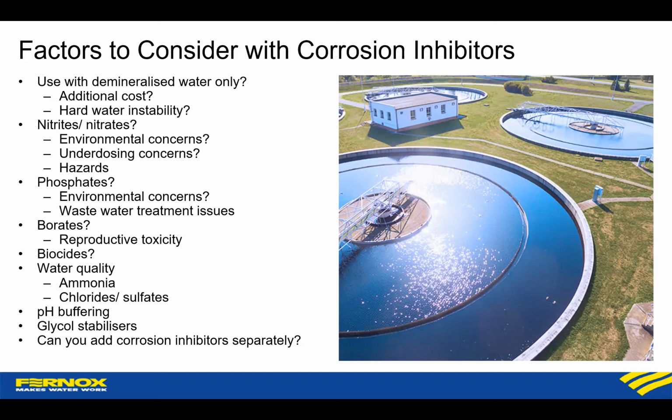Phosphates, as I mentioned earlier, very popular in the US because they're the obvious choice if you need a food grade inhibitor. More and more though, you are seeing states say point blank that you shouldn't be disposing of phosphates into the wastewater stream, because again, similar environmental concerns, they can be an issue to get out of the water system.